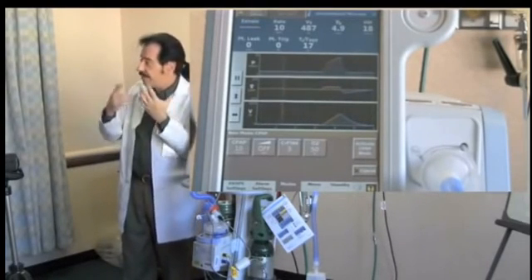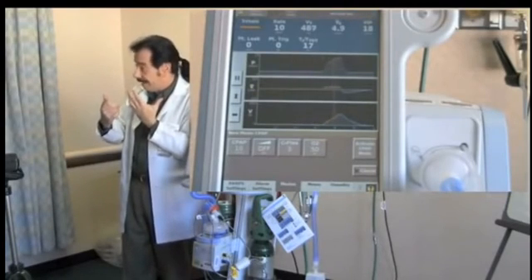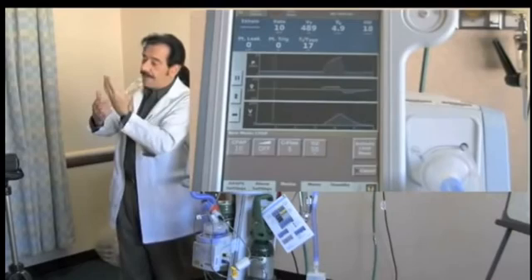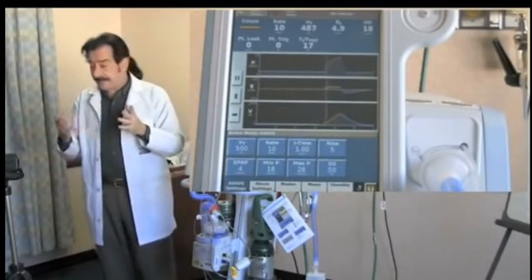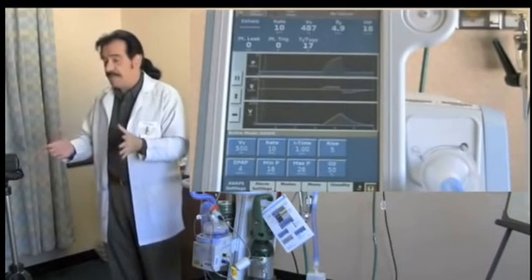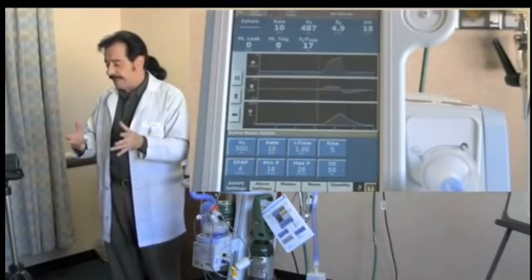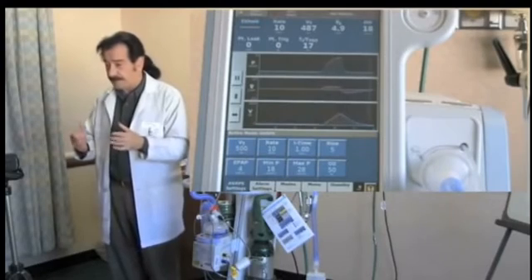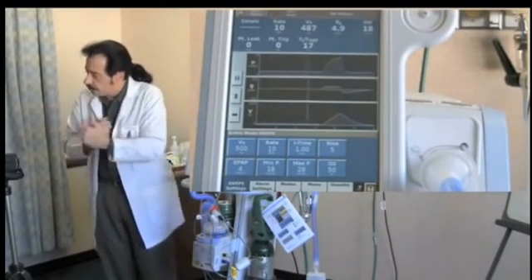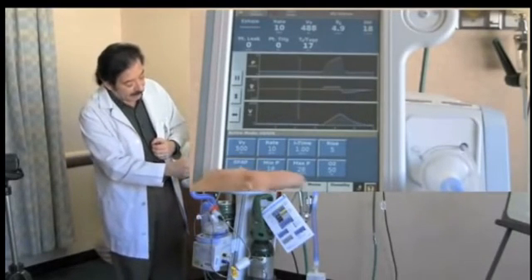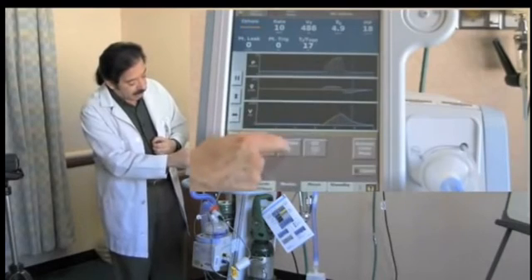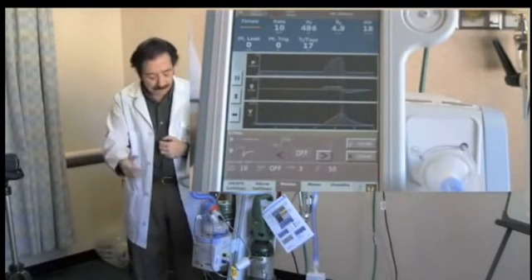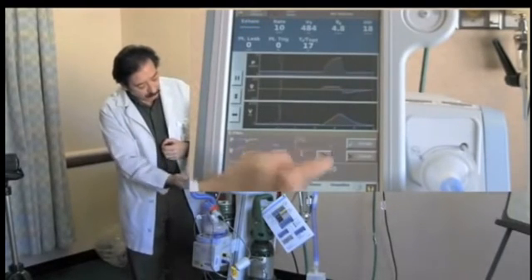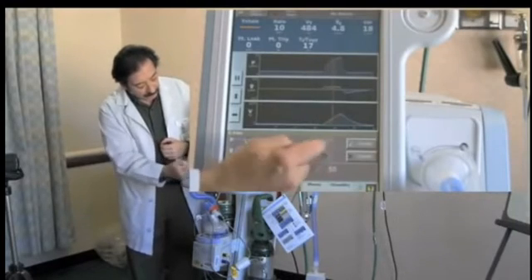But now I've got to breathe out. And I'm breathing out against a 100 mile an hour wind. Well, how hard is that? Kind of hard. As I'm trying to blow out, there's air blowing back in. Patients can become uncomfortable with that, and you may see them activating or using their accessory muscles of exhalation. They're like they have to force the air out against that incoming flow. If that's becoming a problem for the patient, I can go to the C-Flex mode and have a setting of off, meaning that I get constant CPAP, both inspiration and expiration, or I can set it to level 1, level 2, or level 3.